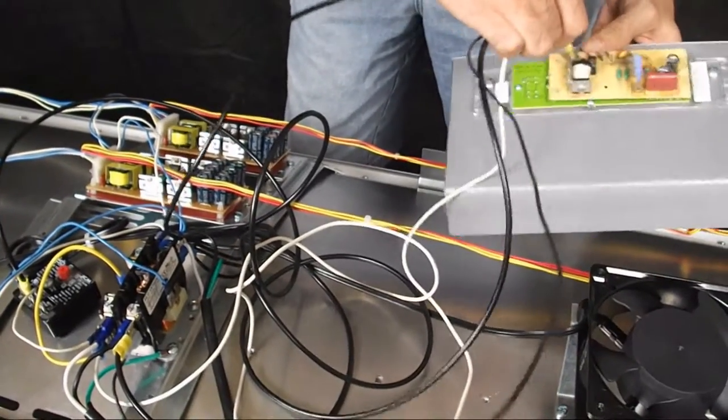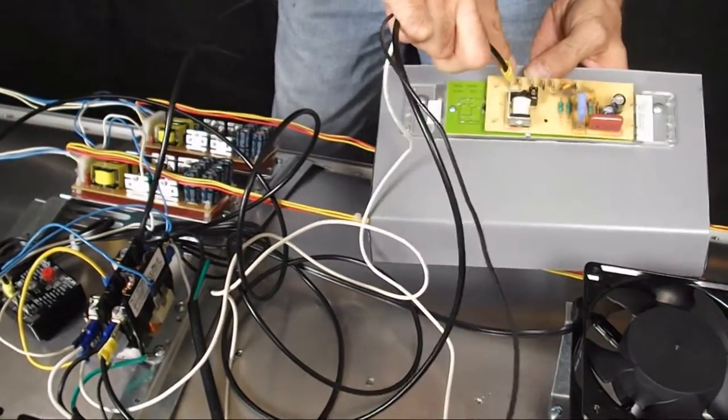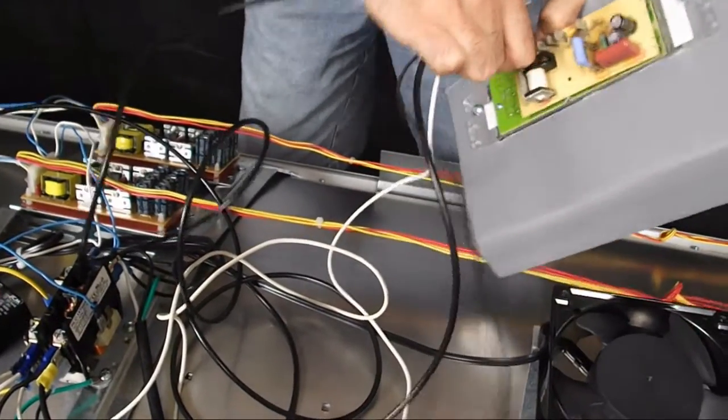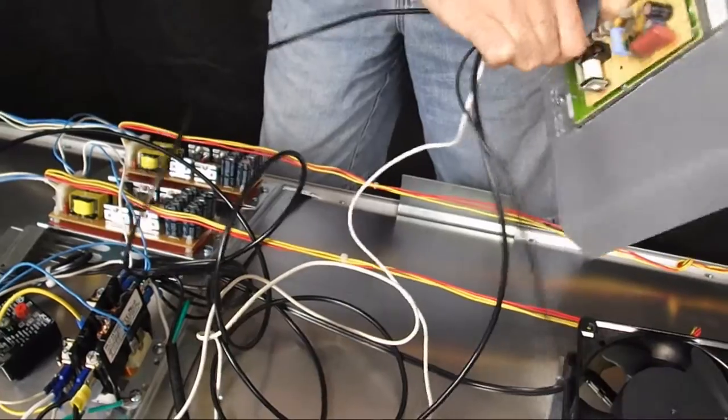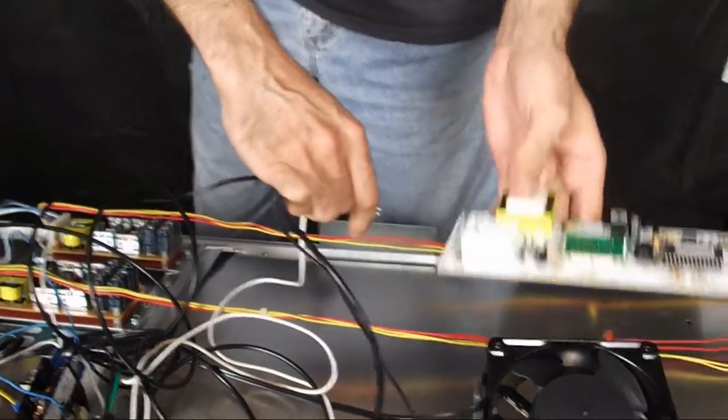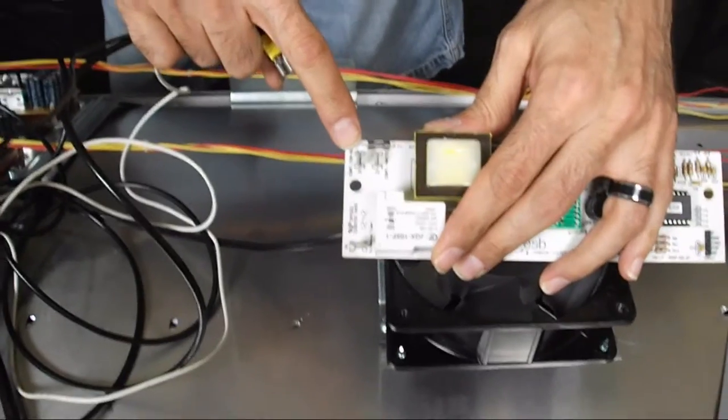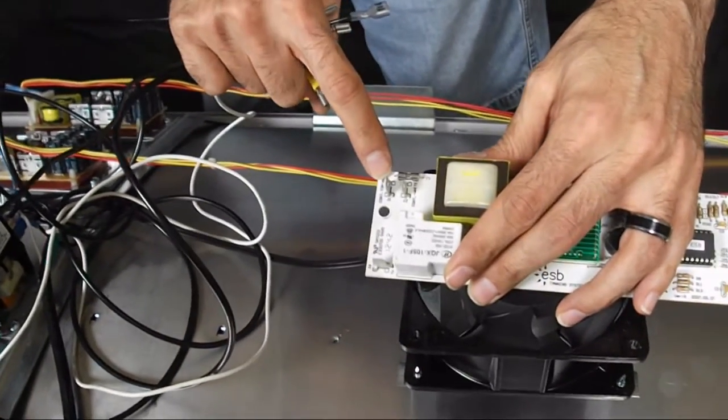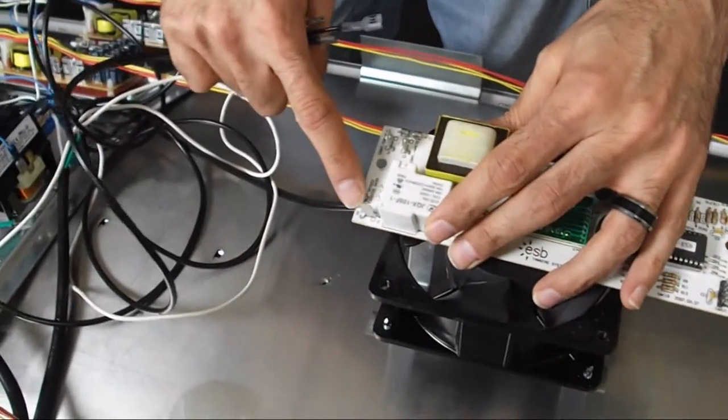And, it's not necessary to note the J terminal configuration, because it's different on the new timer. I'm going to show you how to correctly wire the new timer right now. First, notice that there's only three terminals on this replacement timer: J1, J2, and J6.